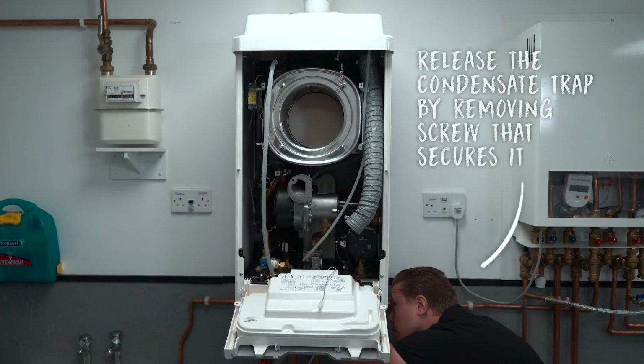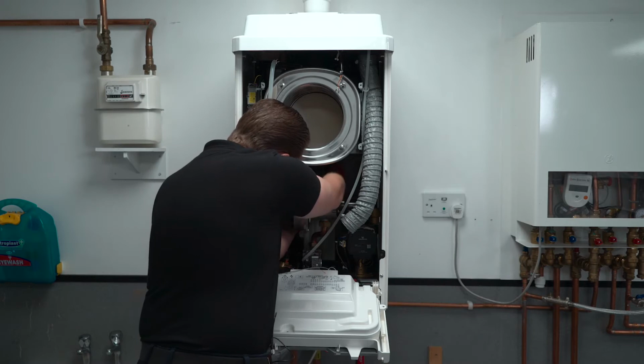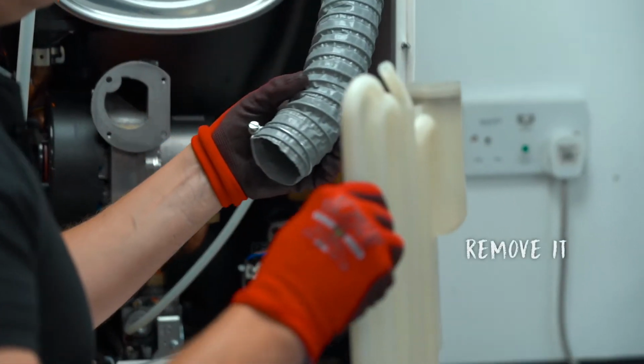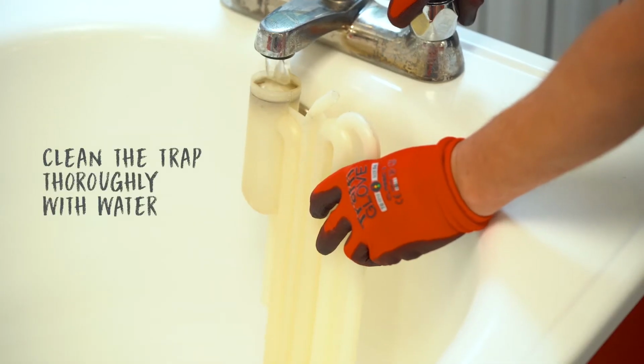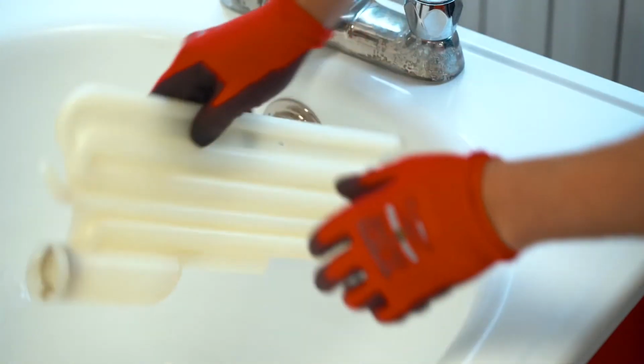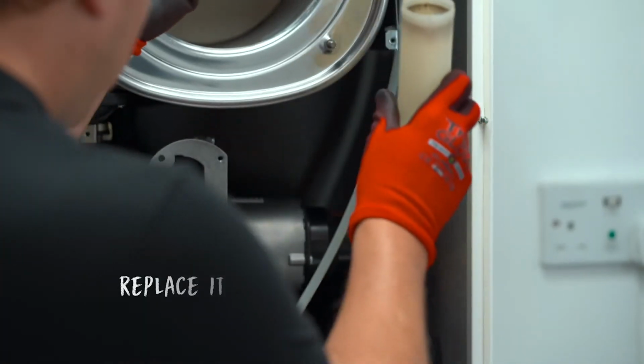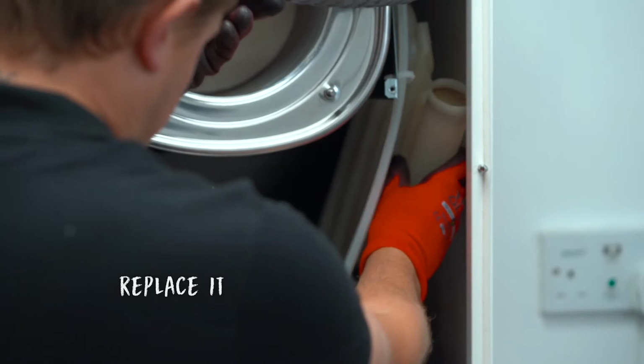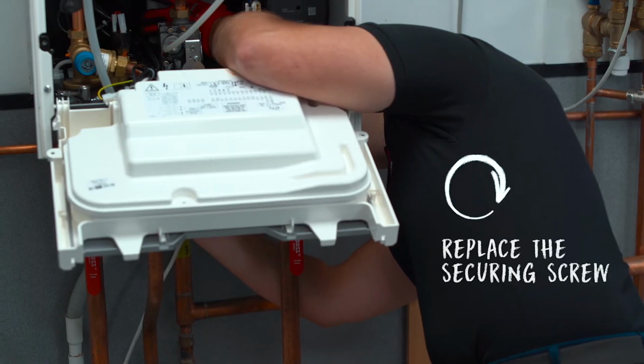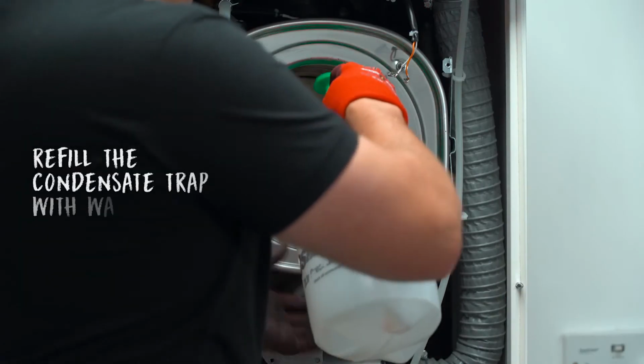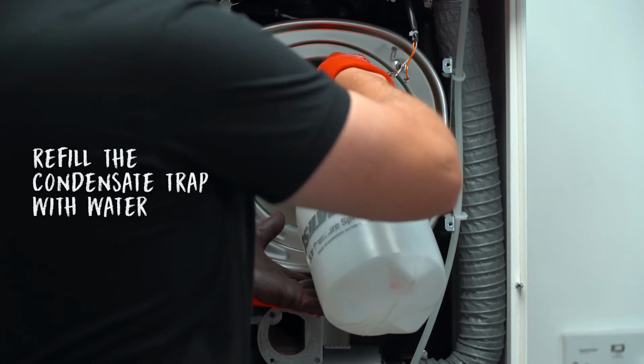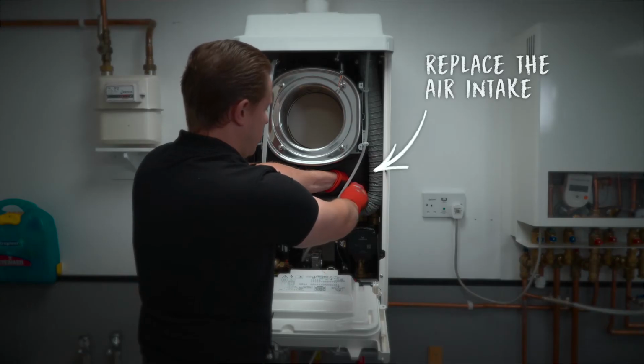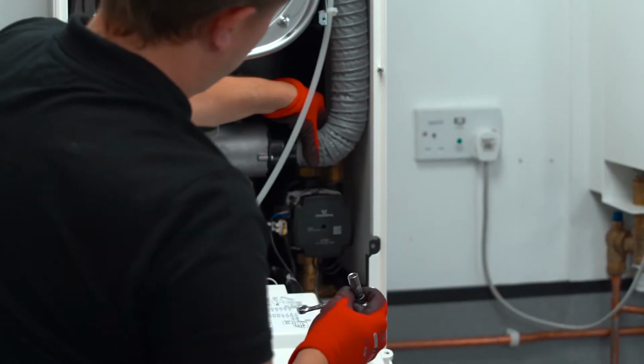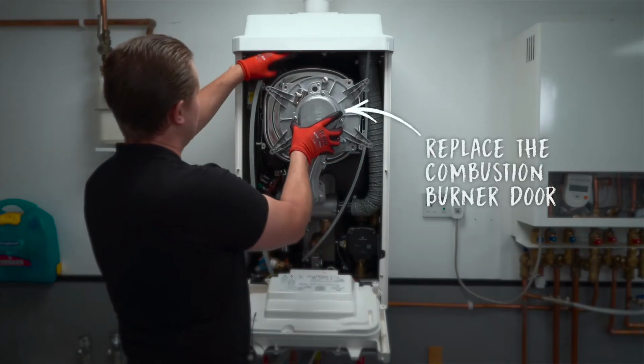Undo the screw securing the condensate trap and then remove the trap from the boiler. Clean the trap thoroughly with water, before replacing both the trap and the securing screw and refilling the trap with water. You can now replace the air intake to the fan and also replace the combustion burner door.